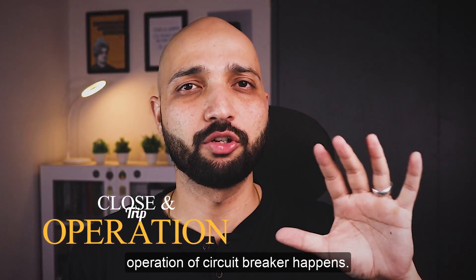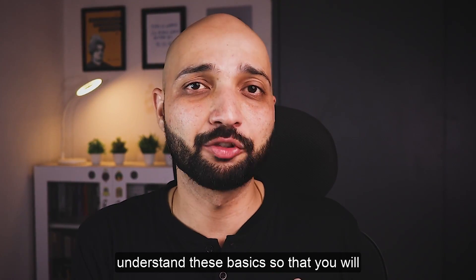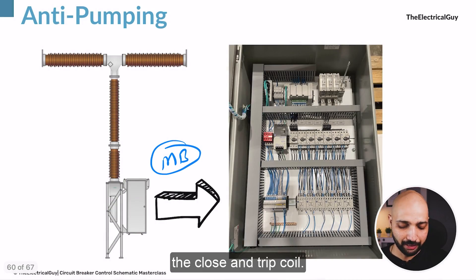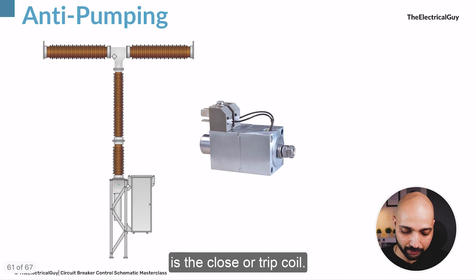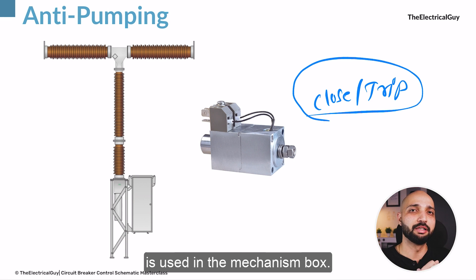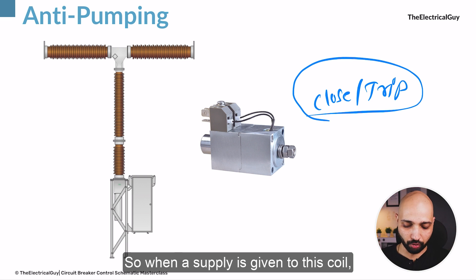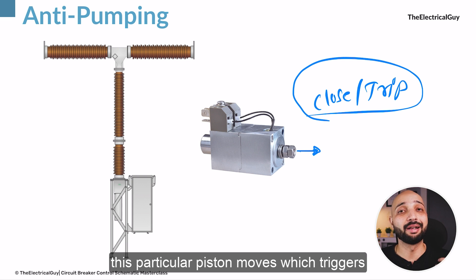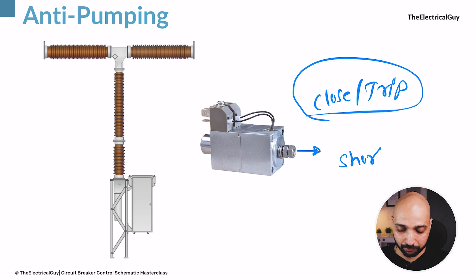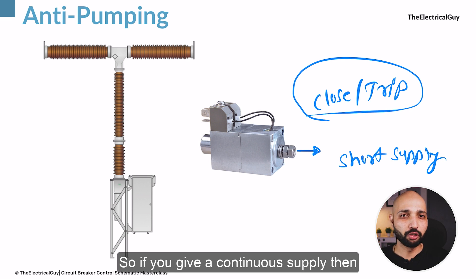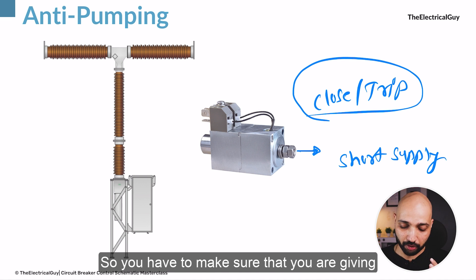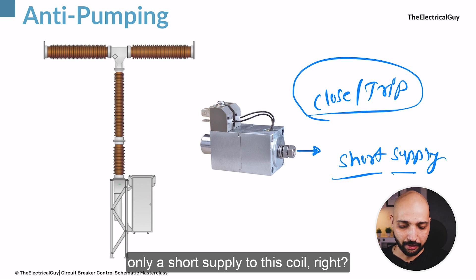Now let us understand how the close and trip operation of the circuit breaker happens — it is really important that you understand these basics so you will understand the dangerous situation of pumping. The close or trip coil is basically a solenoid used in the mechanism box. When a supply is given to this coil, a particular piston moves which triggers the closing or tripping operation. This coil works on a short supply, so if you give a continuous supply it is not good — the coil will burn out.